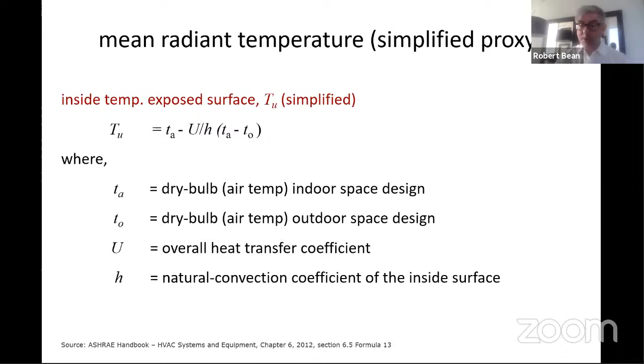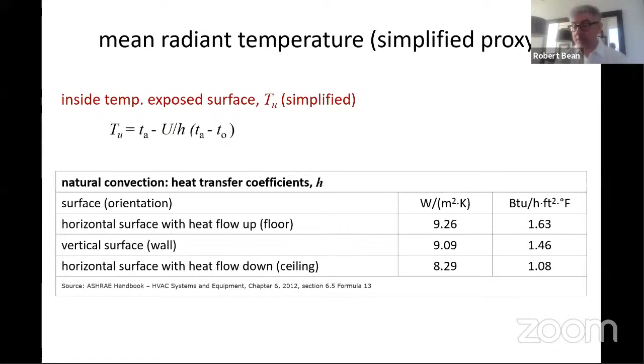So if we know the area, and we know the inside surface temperature of each of the surfaces, we can do a weighted calculation, which is shown on the bottom. So this is a very simple formula. It is in the ASHRAE Handbook, chapter 6, HVAC Systems and Equipment, which provides some description for it. Really, the only thing that you need here to calculate this inside surface temperature is the convective coefficient, which is H, and it changes whether you're on a horizontal surface facing up or facing down, or a vertical surface. So if you know what surface you're working with, then you can just put that particular value in and do the calculation.